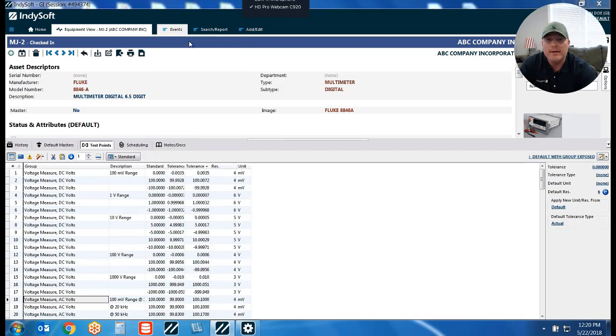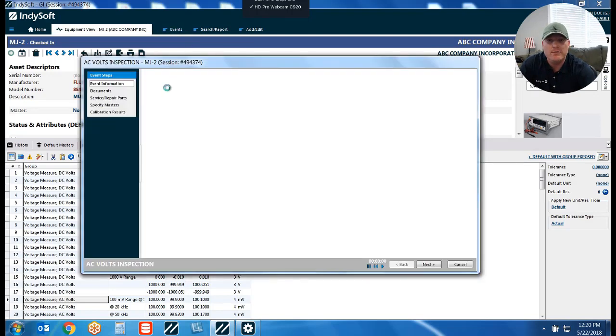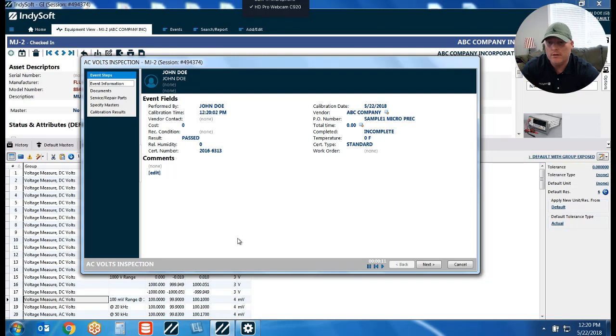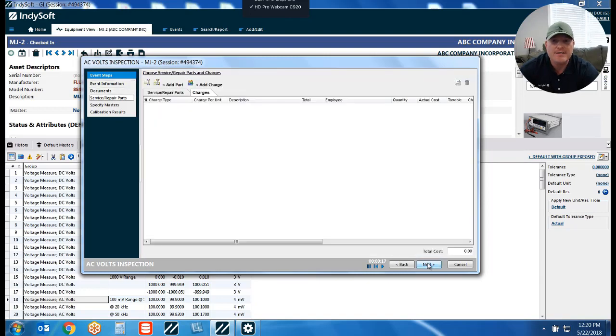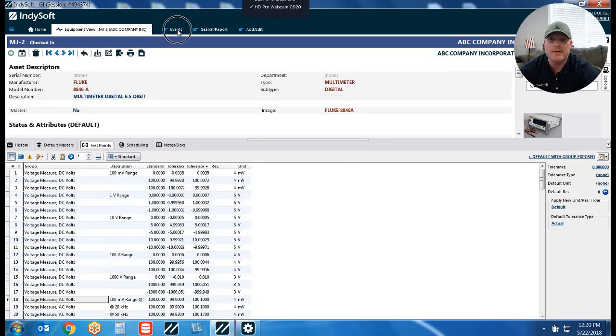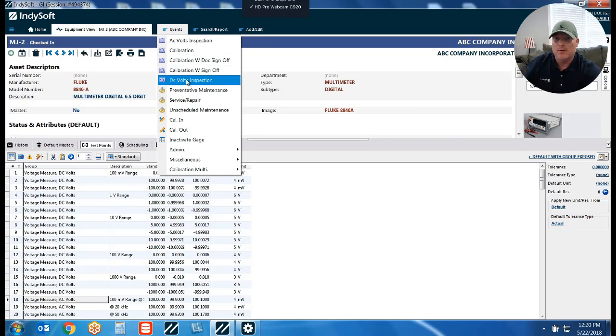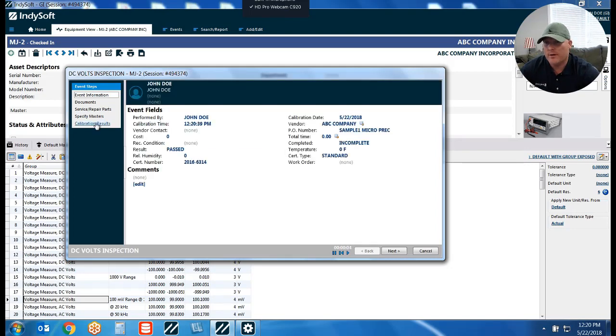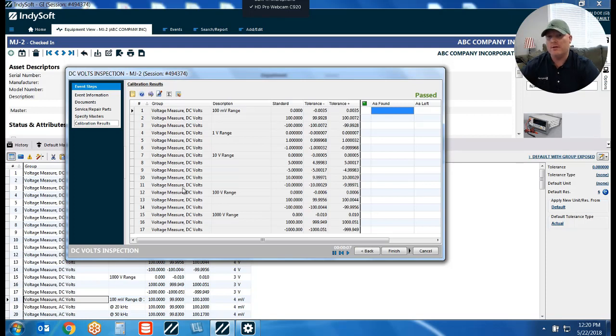If I actually launch my AC volts inspection event, you'll see there is no pop-up. In the torque wrench example we got a pop-up asking for counter or clockwise measurement points, but in this case we only want the AC volts. Proceeding through my event, when we get to the calibration result window the only measurement points or test points that are there are the actual AC volts. The same is applicable if I launch my DC volts inspection event — when I get to my calibration results window, all we're going to see is our DC volts.